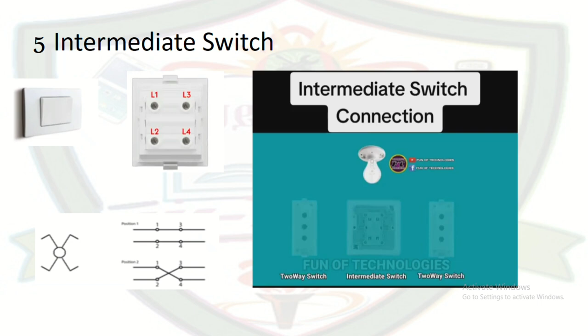This intermediate switch we use as the middle. This is the intermediate switch. This is a two-way switch. This is a two-way switch. This one is the intermediate switch. So at the back, at the middle, the phase is coming, and the neutral is connected to the lamp. The phase is coming to this and out, and enters the second two-way switch at the middle. This phase is connected to the lamp.